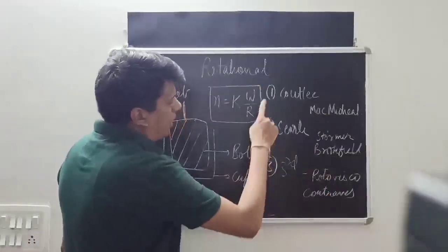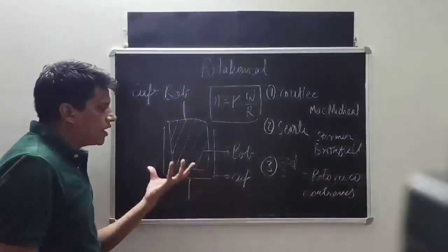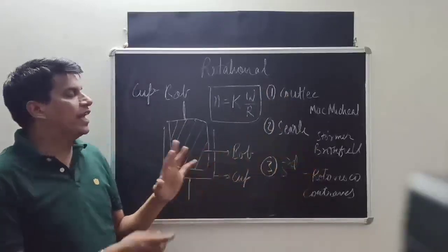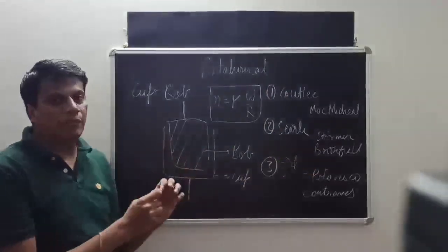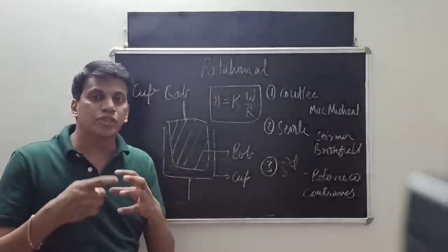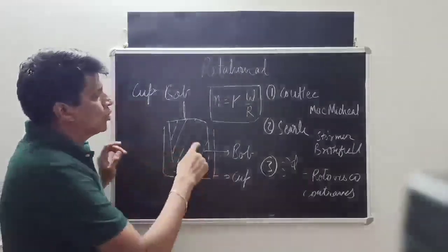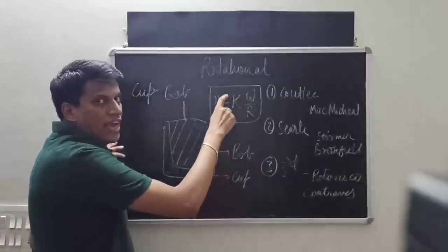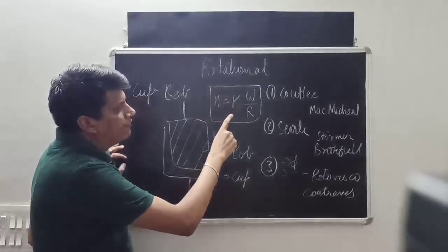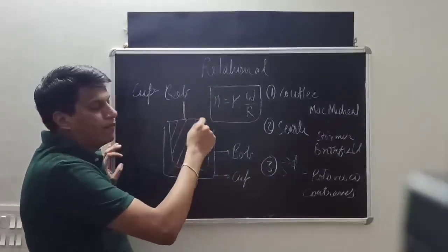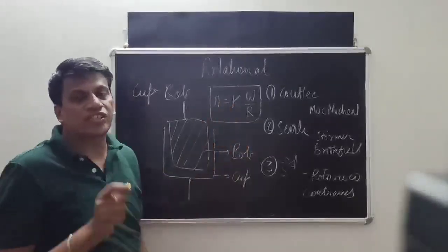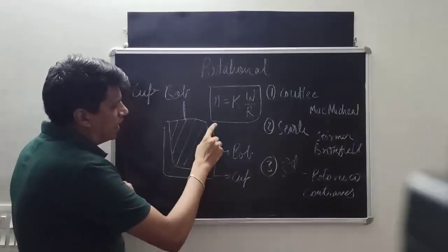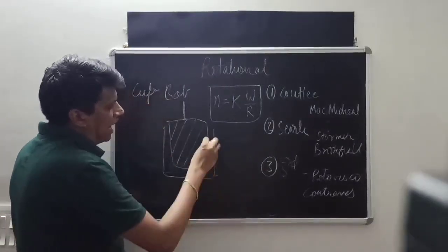This covers the types of cup and bob viscometers. As for how they work, they consist of a cup and a bob — one will rotate and measurement is taken. The measurement records the change in RPM as weight is applied. The equation is: viscosity equals k times W divided by R, where k is the instrument constant, W is the stress or weight applied, and R is the strain or RPM.